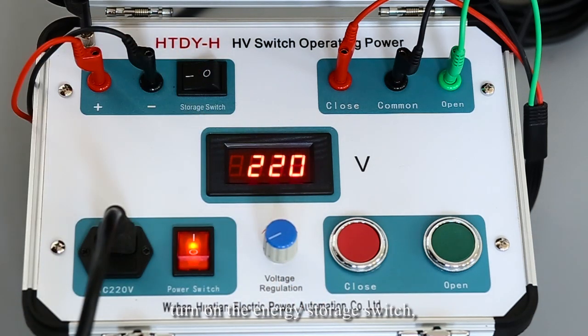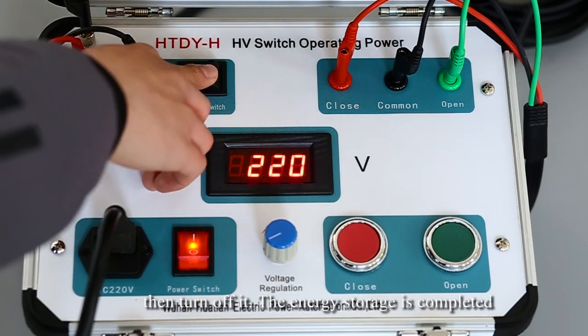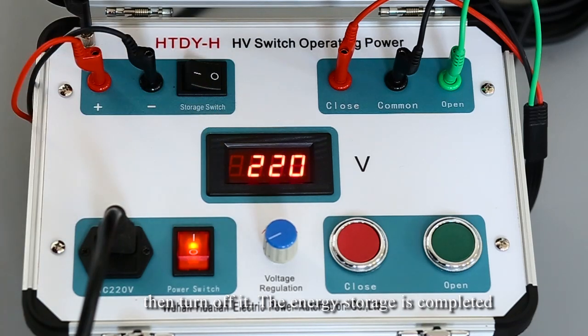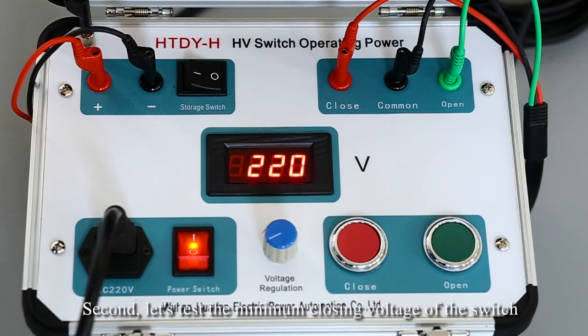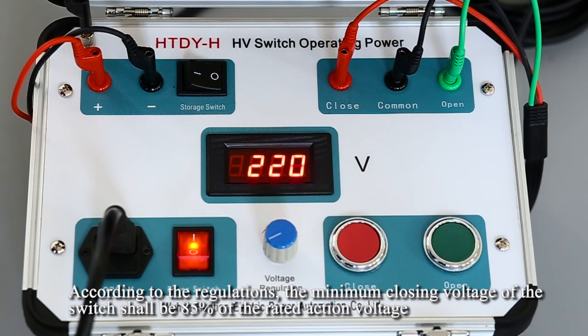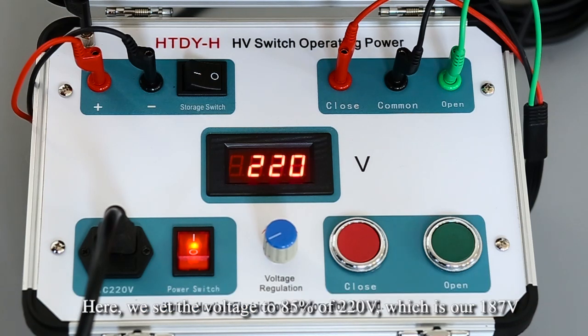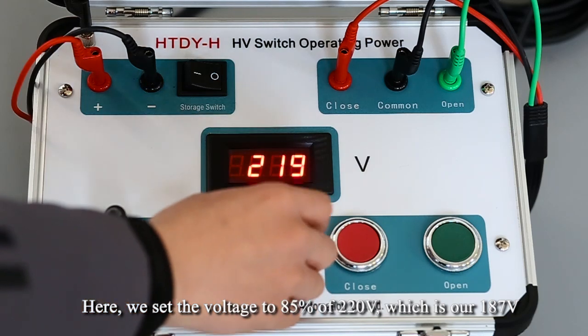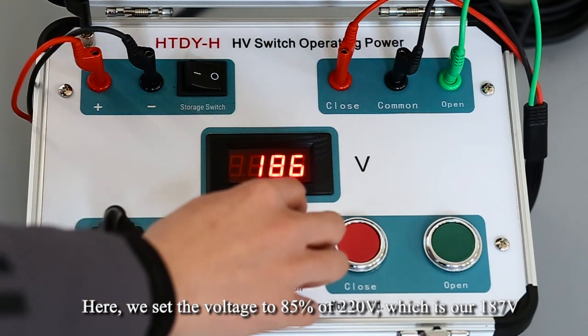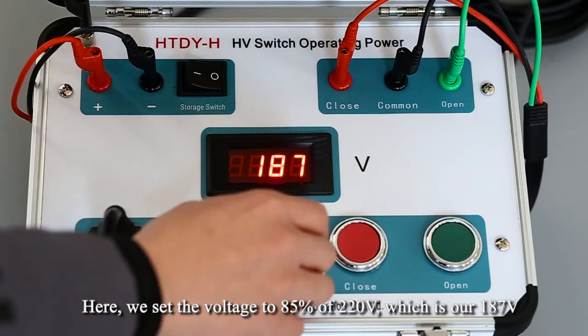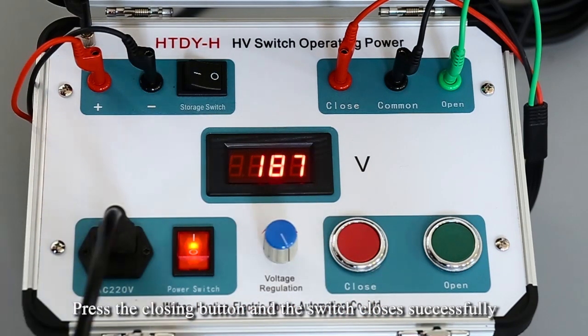Turn on the energy storage switch. Then turn it off. The energy storage is completed. Second, let's test the minimum closing voltage of the switch. According to the regulations, the minimum closing voltage of the switch should be 85% of the rated action voltage. Here, we set the voltage to 85% of 220 volts, which is 187 volts. Press the closing button and the switch closes successfully.